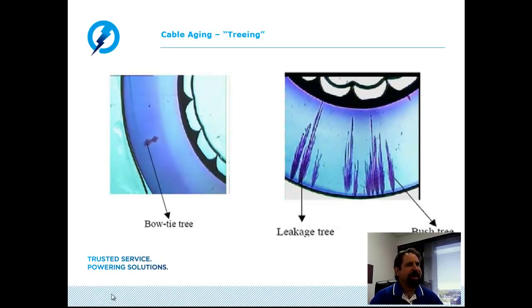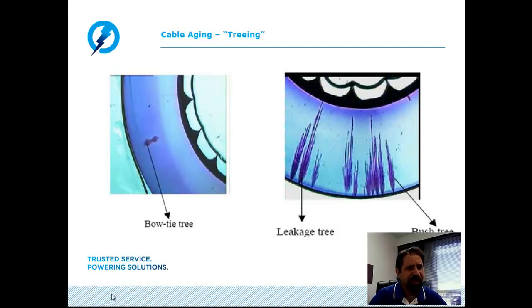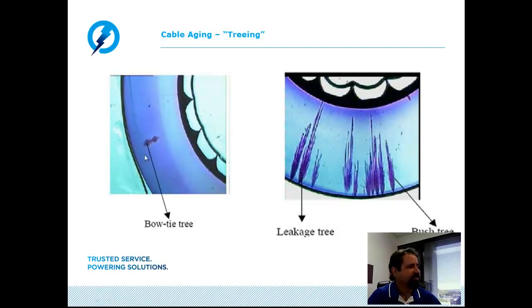Talking about aging characteristics, we can discuss the phenomenon referred to as treeing. Water tree degradation is a major problem for medium voltage extruded dielectric cables, particularly service-aged XLPE and PE style cables. It is perhaps the worst degradation process of the polymeric insulation contributing to cable failure. Water trees form and grow in the presence of moisture, impurities or contamination, and electric field over time. There are generally two types of water trees: the bowtie tree and the vented tree.